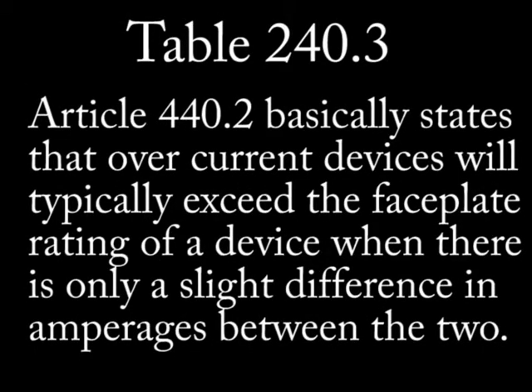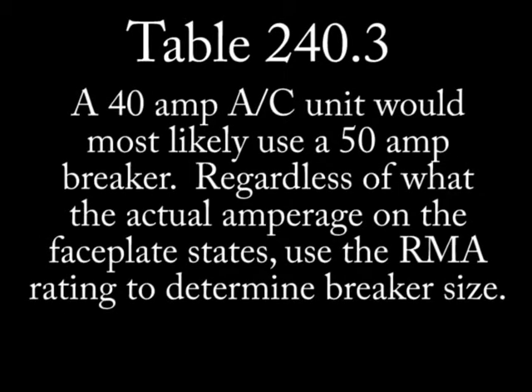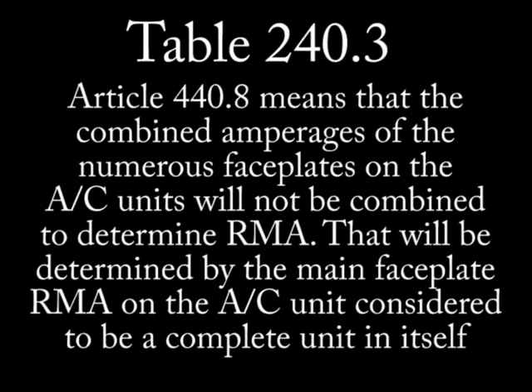What we're looking for is article 440.2, which when simplified means that your overcurrent device or breaker will always exceed the faceplate rating under specific conditions called rounding off. For example, if an HVAC unit has a faceplate rating of 34 amps, then the correct breaker size would be 40 amps. If the faceplate rating is 40 amps, then you would size up to a 50 amp breaker. If a 45 amp breaker were available, that would be the one to use. Article 440.8 means that all devices making up an air conditioner with various faceplate ratings will be considered a single machine, and the unit faceplate will be used to determine the level of overcurrent protection, not a combination of faceplate ratings.